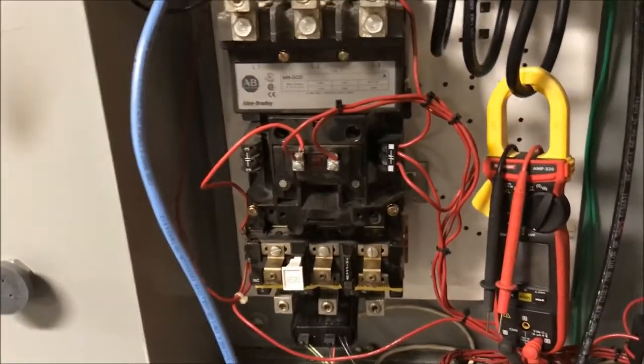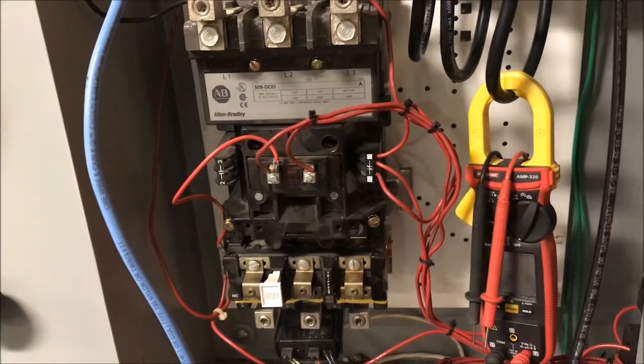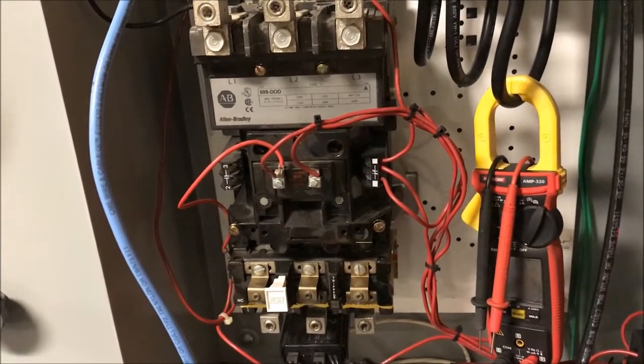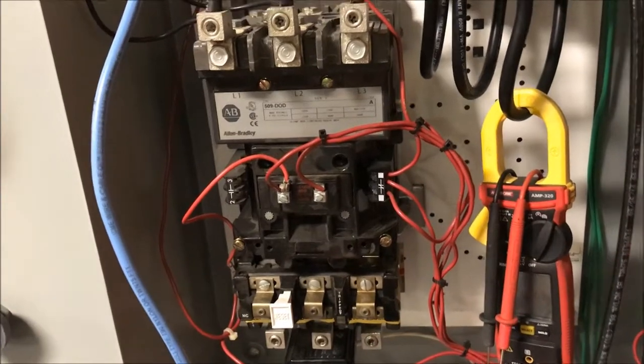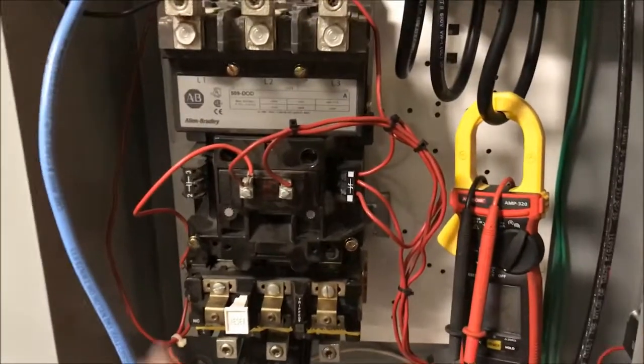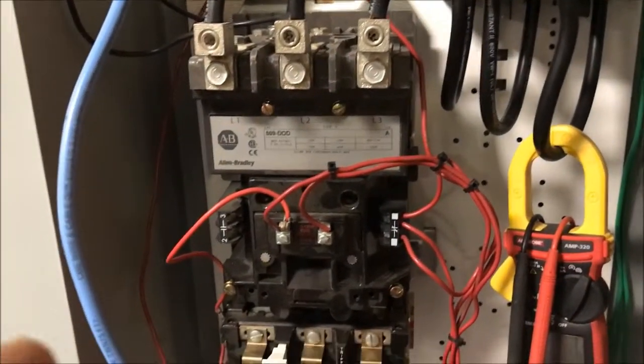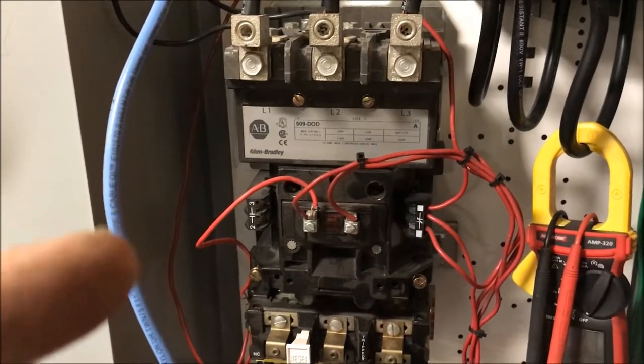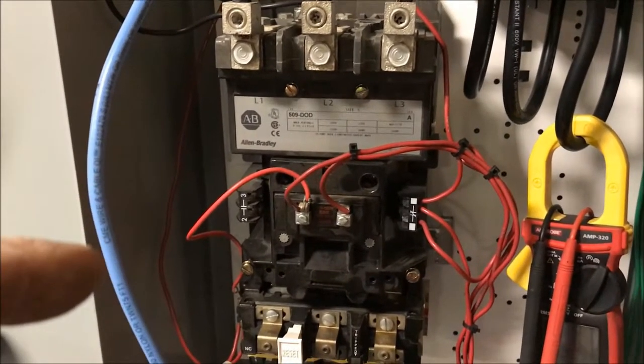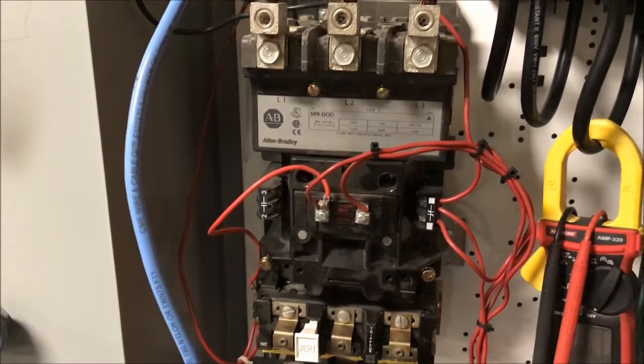L1, L2, and 3 run counterclockwise, and if I'm right, most motors run... if I hook that up, it's going to run counterclockwise, and I need it to run clockwise. If I hook L1, L2, L3 respectively from here to the motor, I think it's going to run reverse, because I think most motors want the shaft to run clockwise.